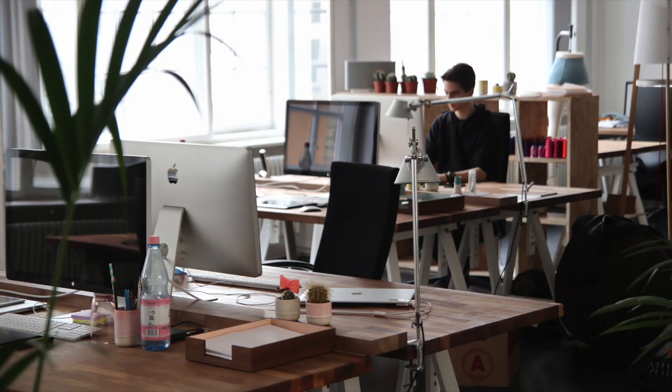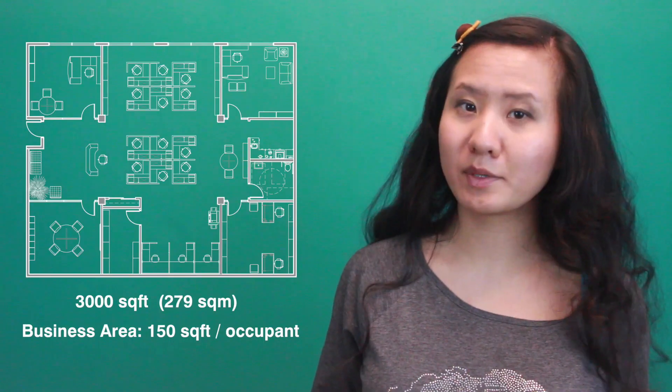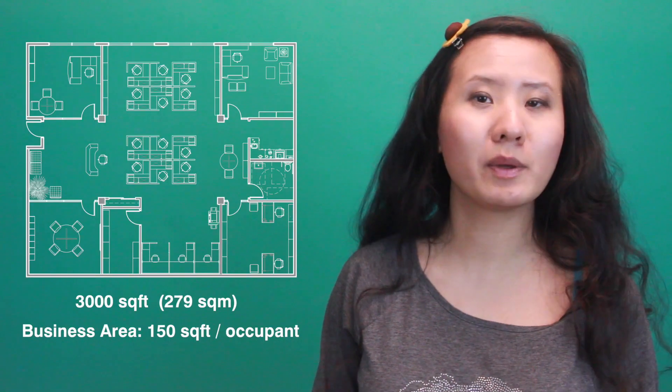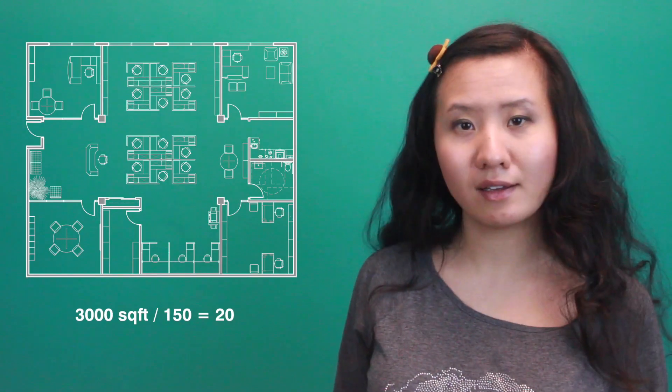In business areas such as an office, the load factor is 150 square feet per occupant. So in the same space, the occupant load for an office would be 20.